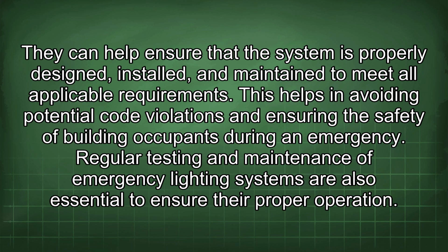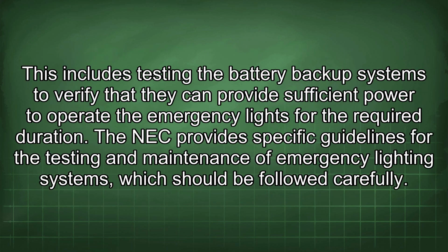Regular testing and maintenance of emergency lighting systems are also essential to ensure their proper operation. This includes testing the battery backup systems to verify that they can provide sufficient power to operate the emergency lights for the required duration. The NEC provides specific guidelines for the testing and maintenance of emergency lighting systems, which should be followed carefully.